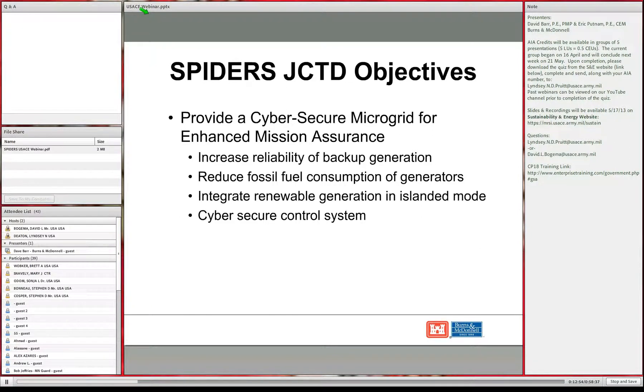SPIDERS is also focused on flexibility—giving the option to go into microgrid mode or stay in the current configuration. This flexibility allows the system to satisfy all life-safety codes, because the default operation is exactly as before: power goes out, generator starts, transfer switch flips. Only after deciding this is a prolonged outage do you choose to enter microgrid mode, either automatically or manually. An unexpected benefit is enhanced generator testing: generators can now be tested at full capacity by connecting them to the real grid rather than only their local loads.